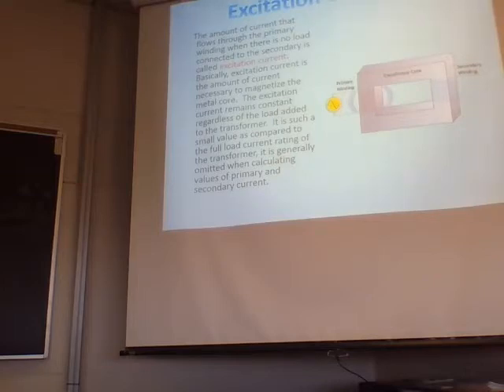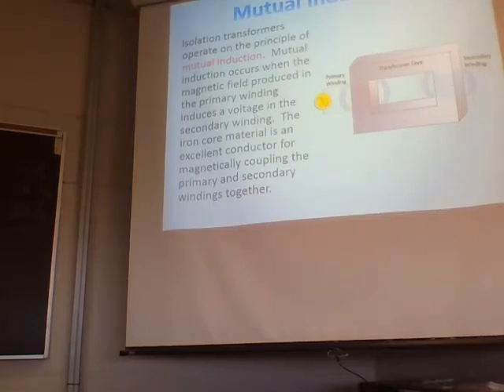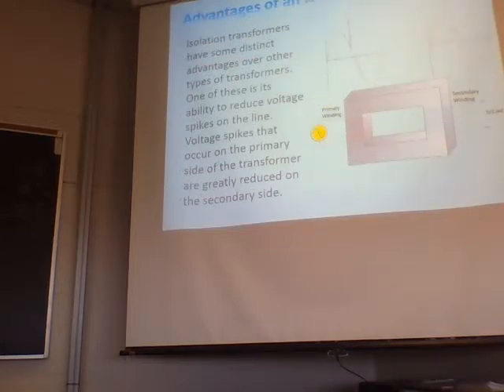Isolation transformers operate on the principle of mutual induction. Mutual induction occurs when the magnetic field produced in the primary winding induces a voltage in the secondary winding. The iron core material is an excellent conductor for magnetically coupling the primary and secondary windings together. Isolation transformers have some distinct advantages over other types of transformers. One of these is their ability to reduce voltage spikes in the line. Voltage spikes that occur on the primary side of the transformer are greatly reduced on the secondary side.